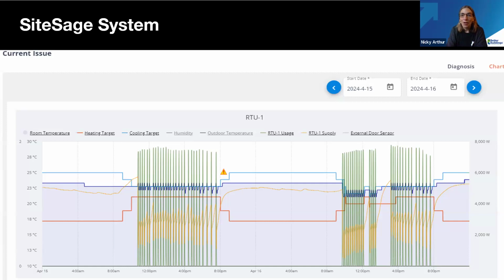In this case, a call to the shop resolved the issue. They were having some unseasonably warm weather locally, and the doors had been left open for a long period of time, which was causing the system to try to cool but not be able to get to the right temperature. So we asked them to close the doors for an hour to see if it stabilized, and that did solve the problem. Easy fix, but it's been really helpful for the HVAC technician to be able to dig in here and pull these logs.